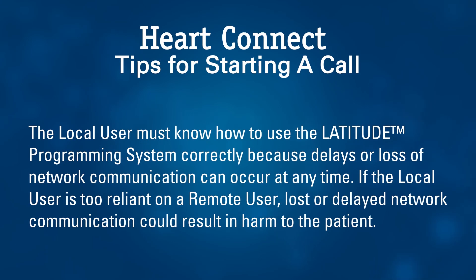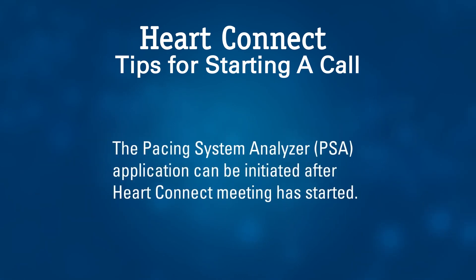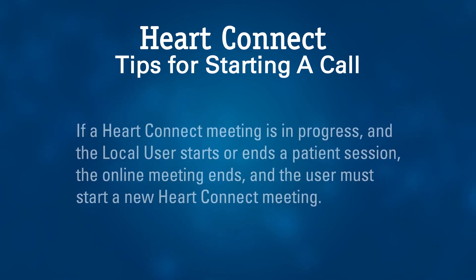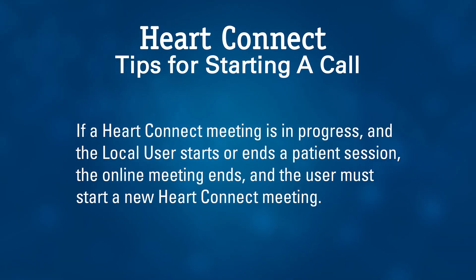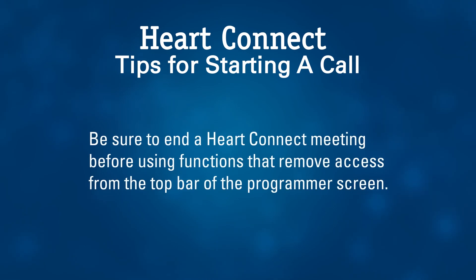The local user must know how to use the connected medical equipment correctly, because delays or loss of network communication can occur at any time. If the local user is too reliant on a remote user, lost or delayed network communication could result in harm to the patient. The pacing system analyzer, PSA application, can be initiated after a HeartConnect meeting has started. If a HeartConnect meeting is in progress and the local user starts or ends a patient session, the online meeting ends and the user must start a new HeartConnect meeting. Be sure to end a HeartConnect meeting before using functions that remove access from the top bar of the programmer screen.